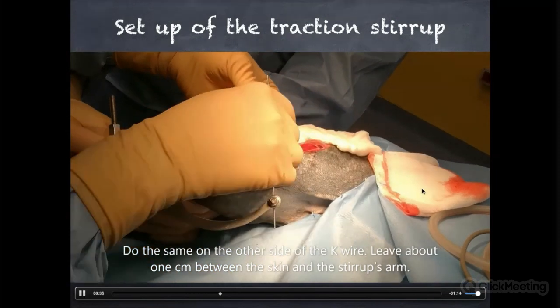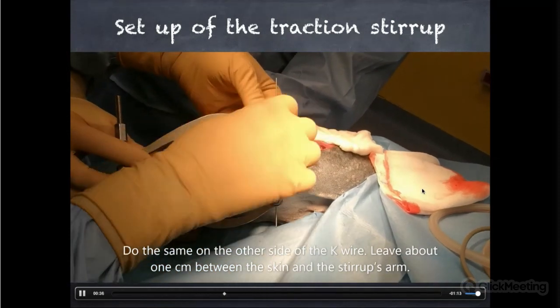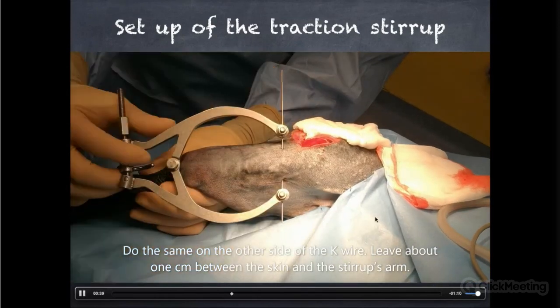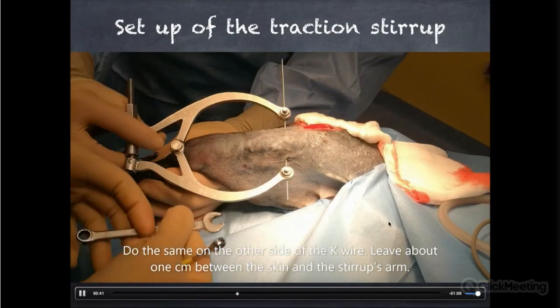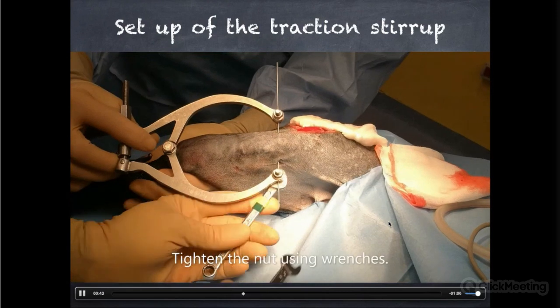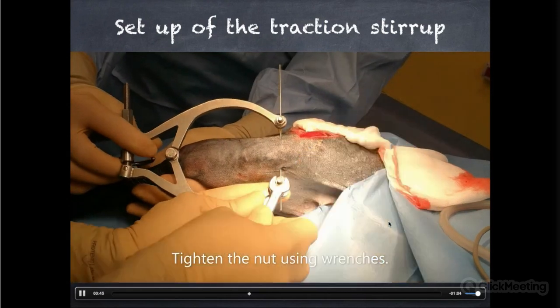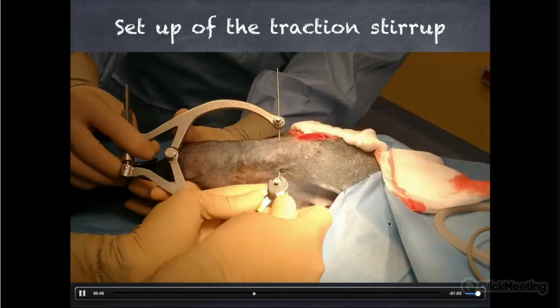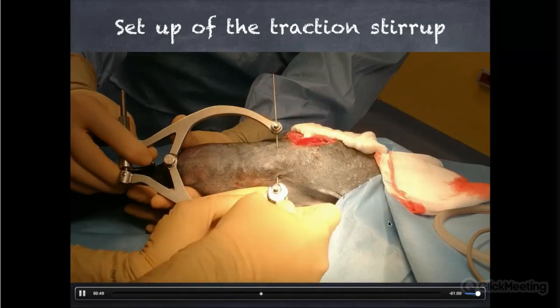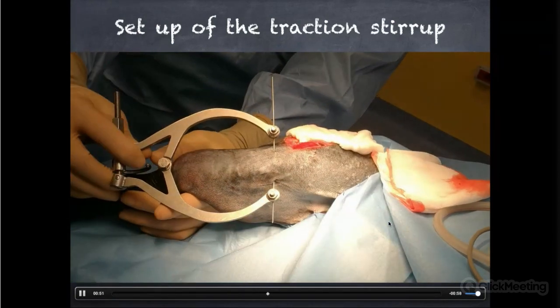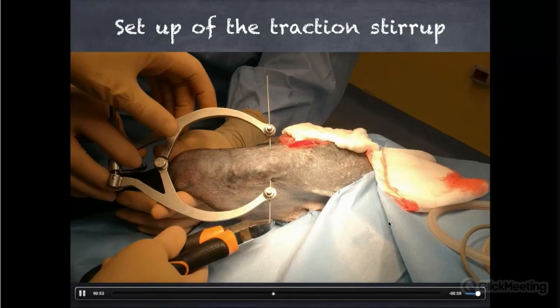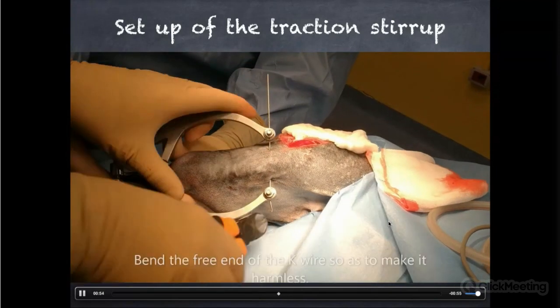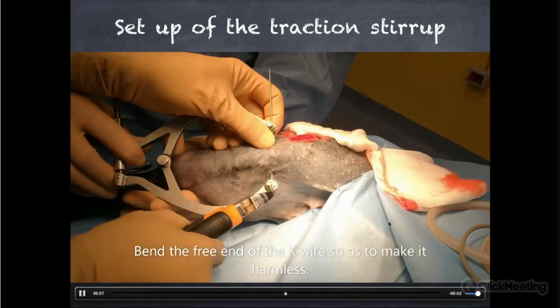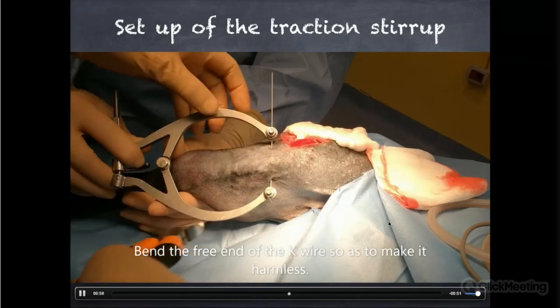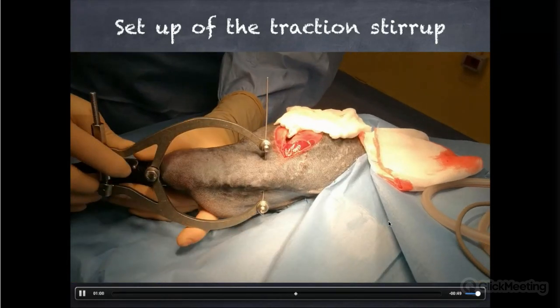So we are connecting the K-wire to the arms of the stirrup, and once they are connected, we are tightening the nuts in order to stabilize the K-wire. Who knows the technique for circular external fixators knows that this is just standard procedure, okay? Very straightforward, very simple technique.